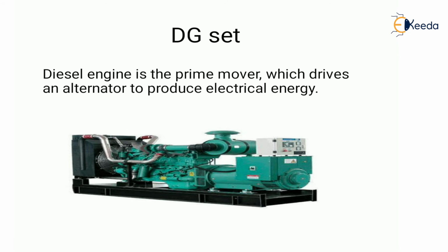The diesel power plant is more advantageous because of its initial cost, quick starting and stopping time, and it does not require any warm up period. Therefore, the standby losses are not present. Here in the DG set, the engine is the main component which develops the mechanical power, and the engine is directly coupled to the alternator. The internal combustion engine may work on 4-stroke cycle or 2-stroke cycle.